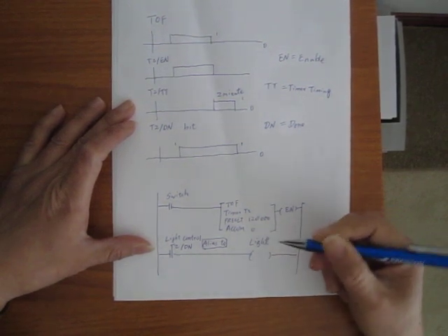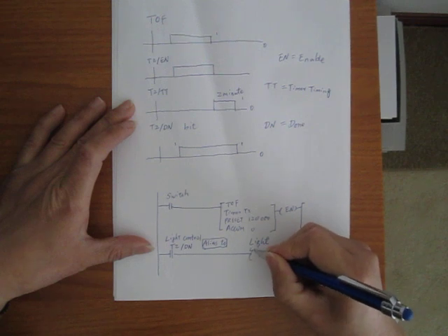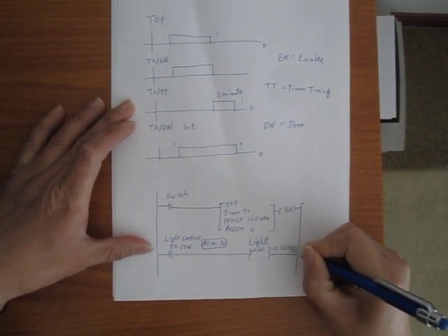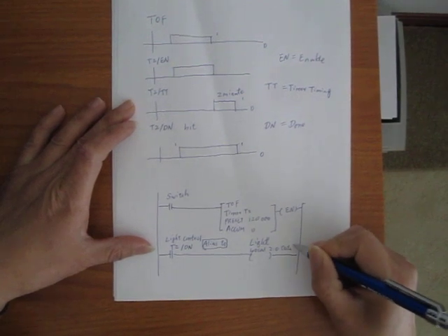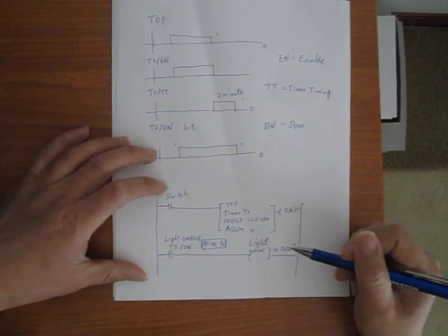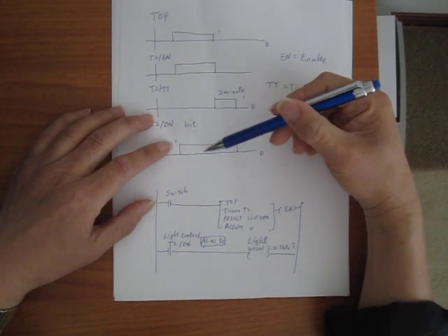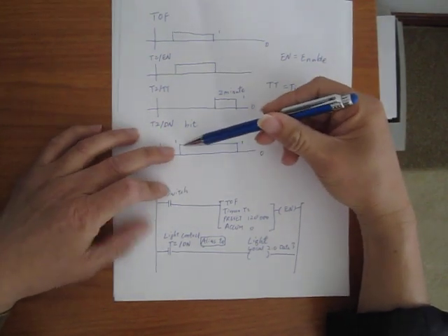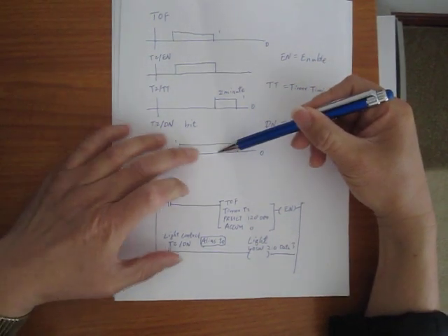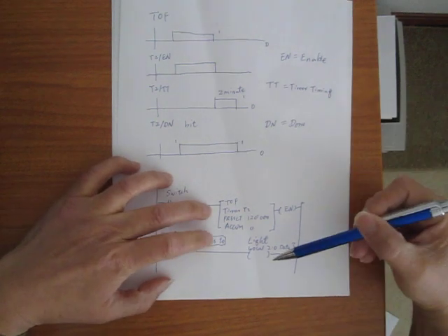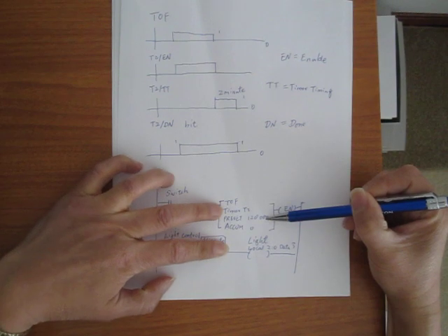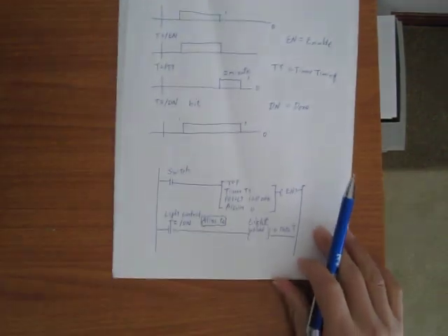And then I'm going to have this one as a light. Certainly this light is going to be wired to a local 2.0 data, let's say data 3, somehow like that. And this will be a switch controlled light. When you turn the switch on, the light will be on. When you turn the switch off, the light will be on for 2 more minutes.